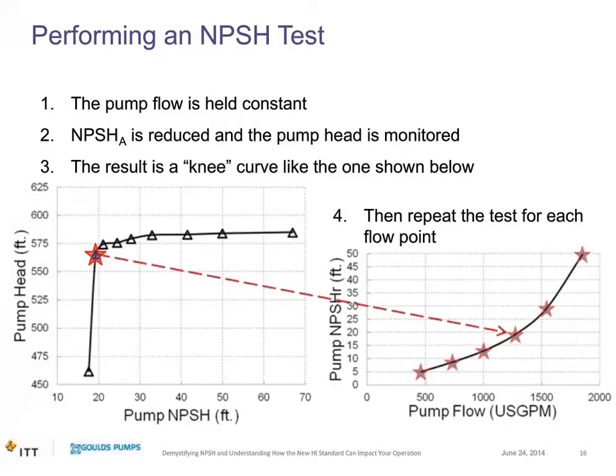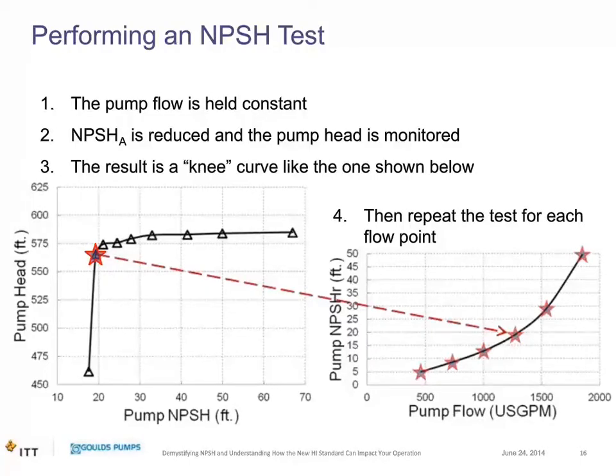Rich took you through calculating NPSHA — the system side. Now I'll talk about NPSH-R or NPSH-3, which are essentially equivalent. Interestingly, people ask how we calculate NPSH-R as a manufacturer — and the answer is we don't calculate it; we test it. Tests are fun, and NPSH-R is a critical quantity that needs to be validated through testing.